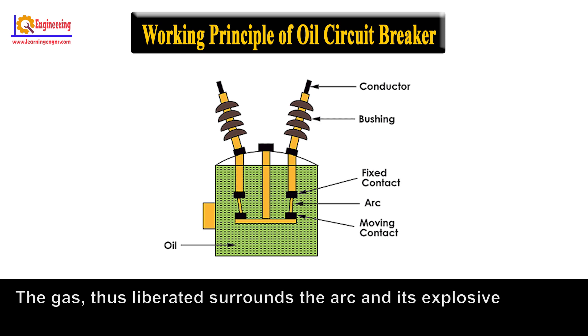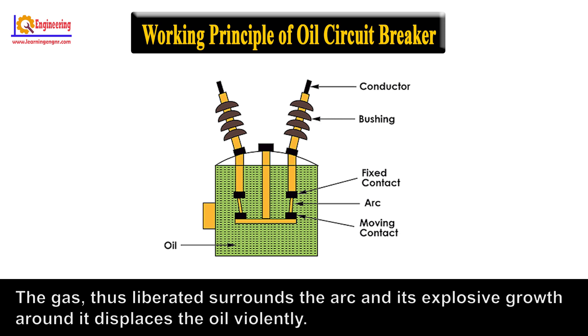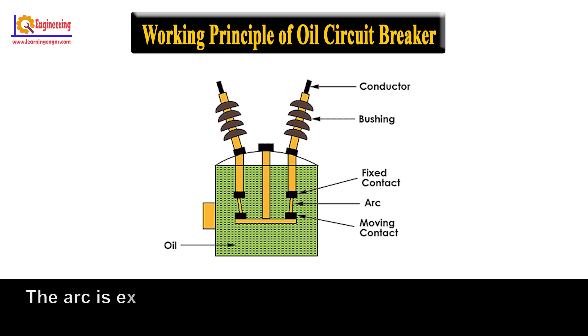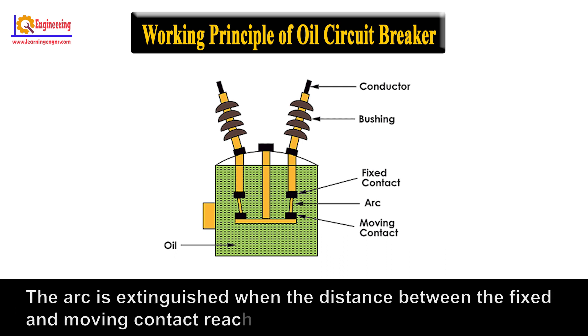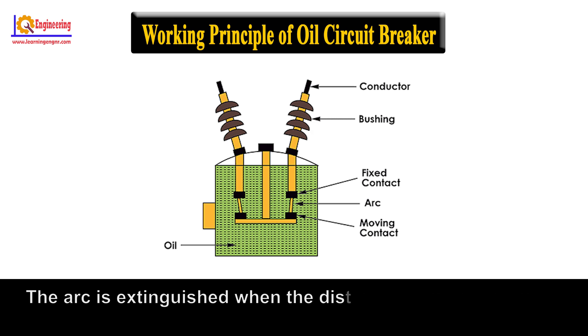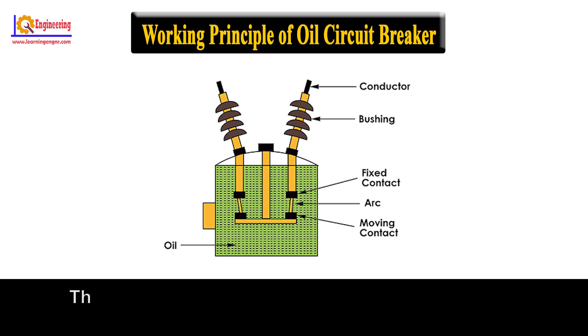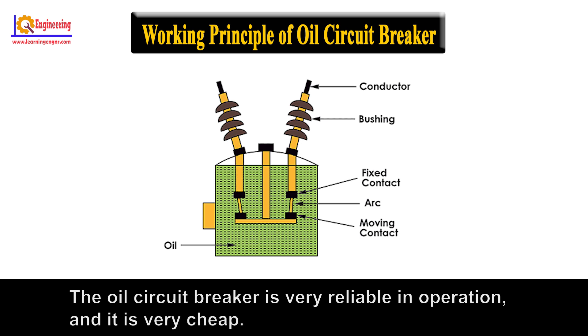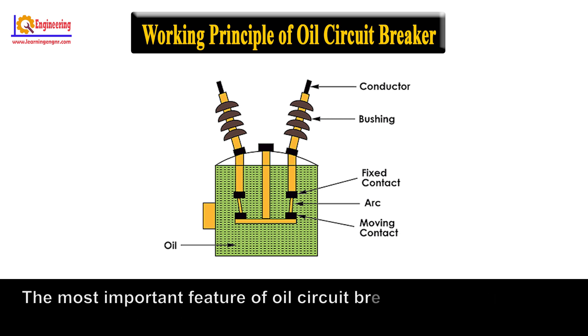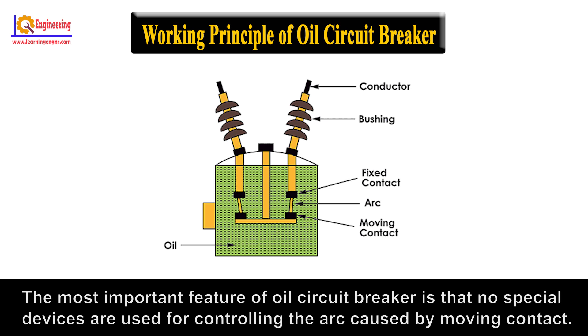The gas thus liberated surrounds the arc, and its explosive growth around it displaces the oil violently. The arc is extinguished when the distance between the fixed and moving contacts reaches a certain critical value, depending on the arc current and recovery voltage. The oil circuit breaker is very reliable in operation and it is very cheap. The most important feature is that no special devices are used for controlling the arc caused by the moving contact.